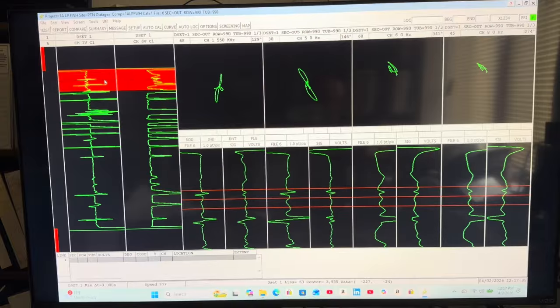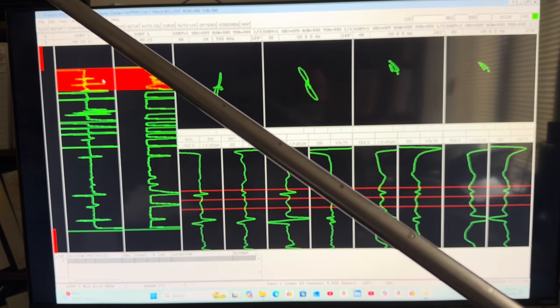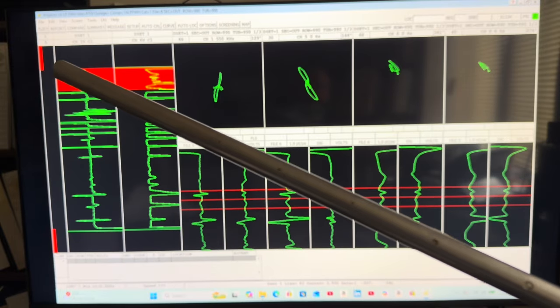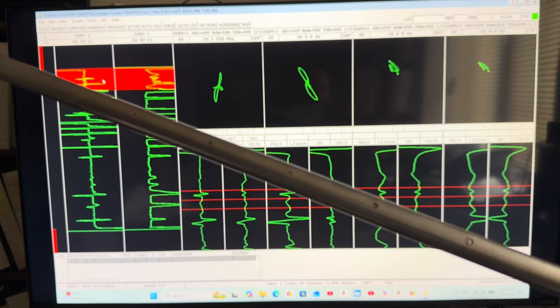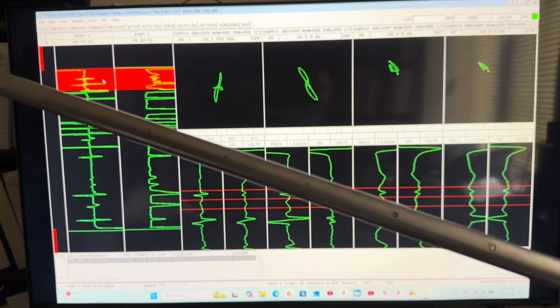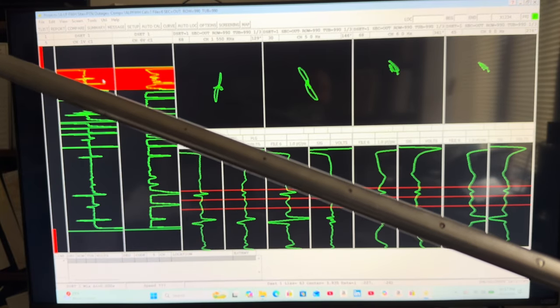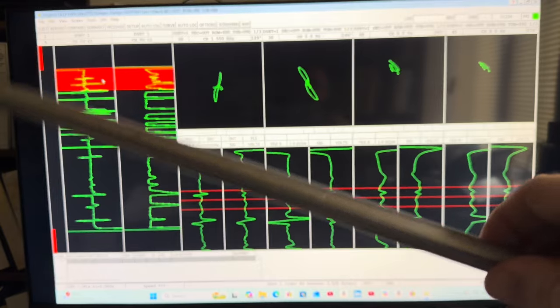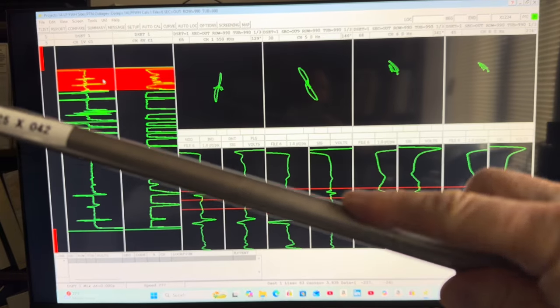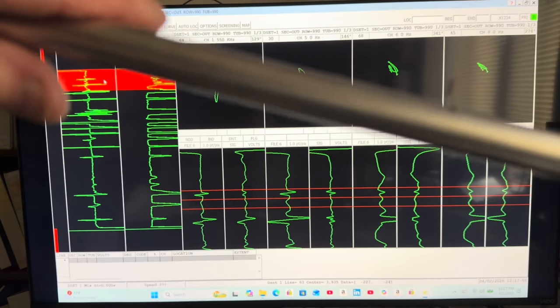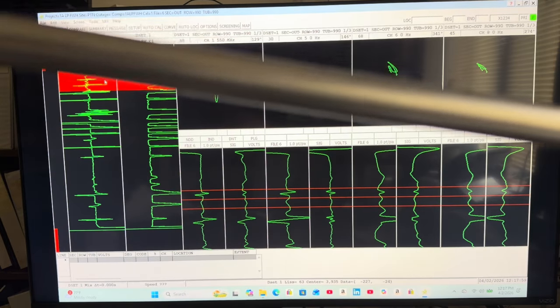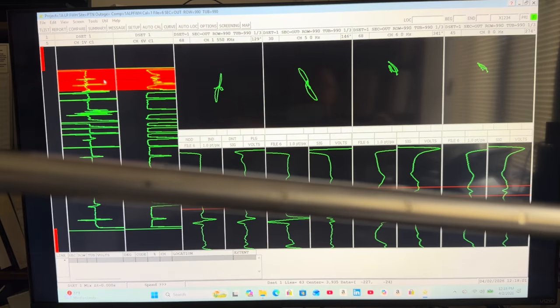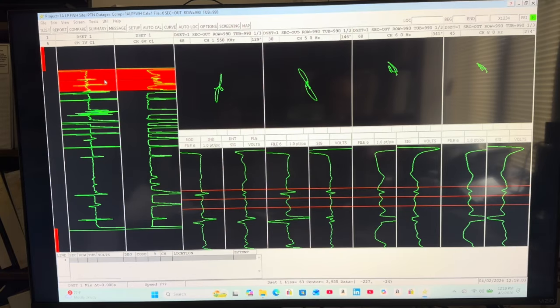Now, one of the first things I want to talk about is calibration tube. ASME calibration tubes contain specifically machined defects such as flat bottom holes. We got some groove wear on this end. Where's the groove wear? Here we got an OD groove, and most of the rest are just flat bottom holes in this particular cal standard.